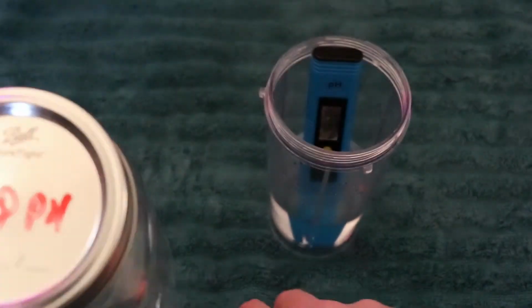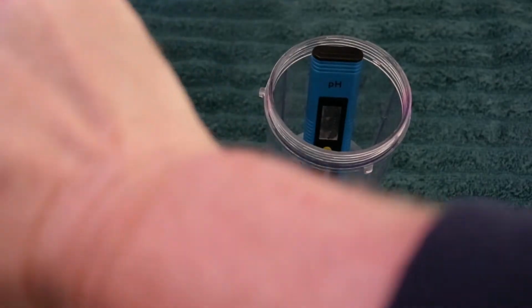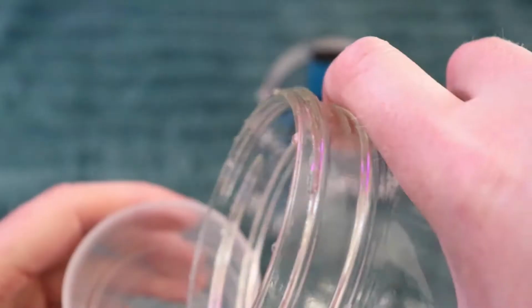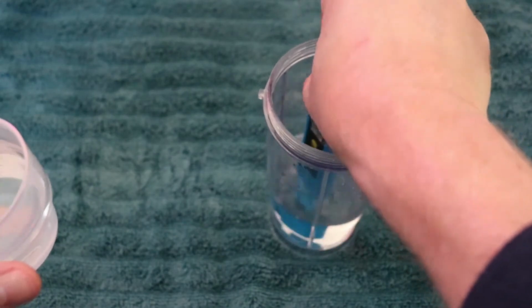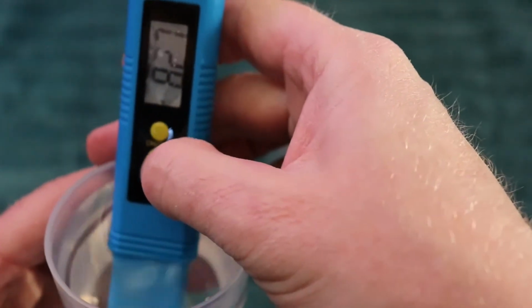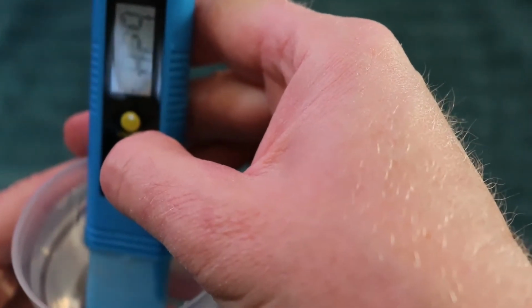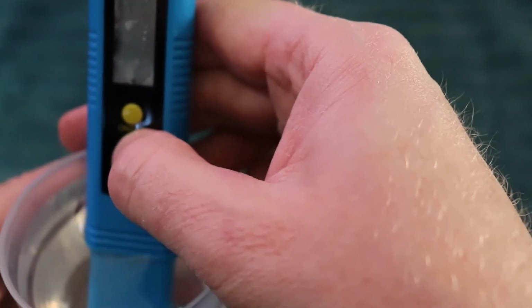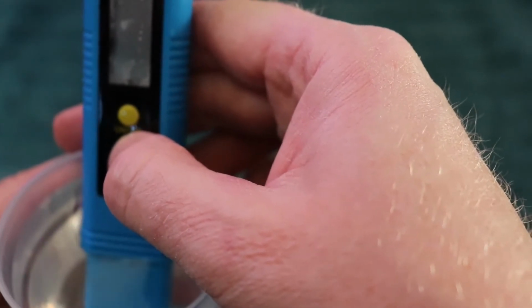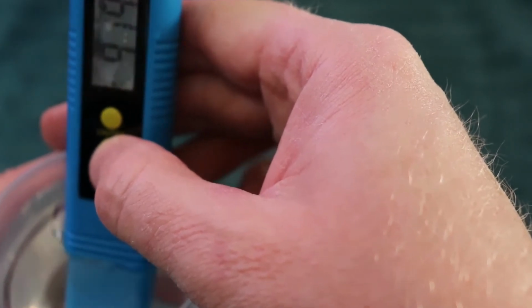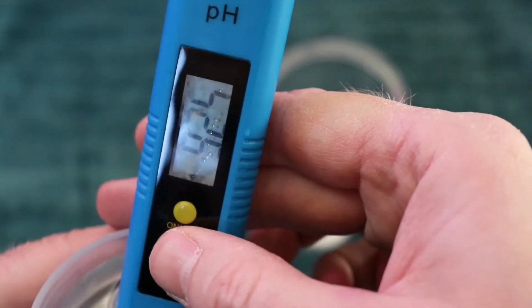Now I have the 9.18 pH. Shake it up, make sure it's mixed. Dry out your testing container. Pour in the 9.18. Mix your probe around in your distilled water. Make sure there's no residue left over. Then put it in your 9.18. Press and hold the cal button for 5 seconds. Press cal again, it'll flash 4.01. Press cal again, now it'll flash 9.18. And after it's done, it'll be calibrated.